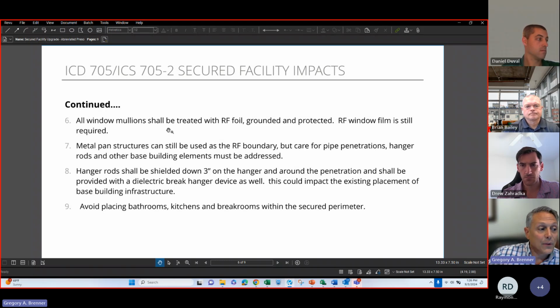Hanger rods shall be shielded down 3 inches on the hanger and around the penetration. Dielectric breaks are required on any hanging device, so even for your ceiling ACT hangers you've got to have a dielectric break on that hanger. They're available, they vary in size and cost, and it's more of a labor element now. Before, we weren't having to do that; we were just grounding and not having to put the dielectric break.